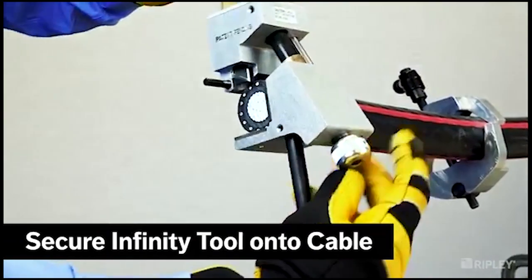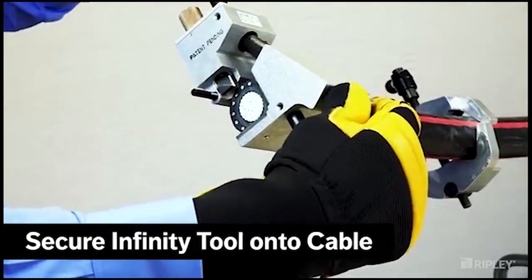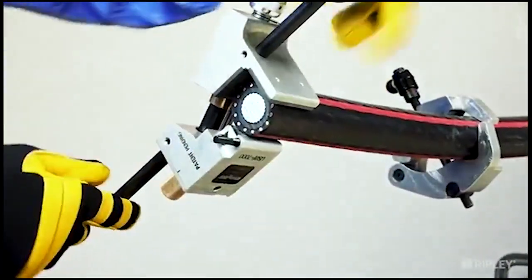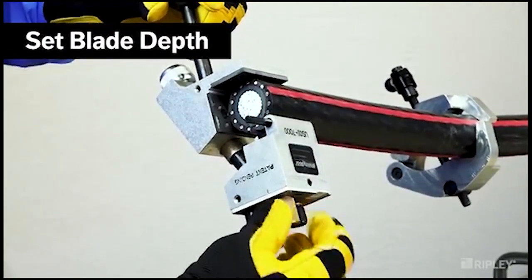Install the tool around the cable with the blade edge overhanging the cable end. Set the blade depth between 15 to 20 thousandths above the concentric wires or metallic shielding.